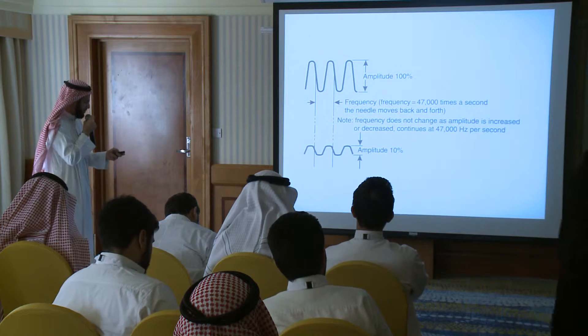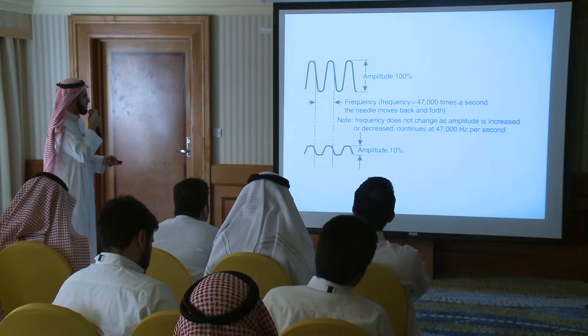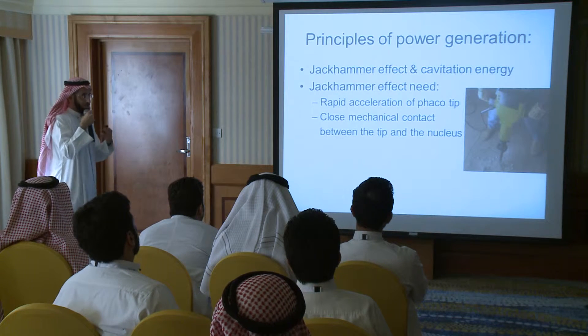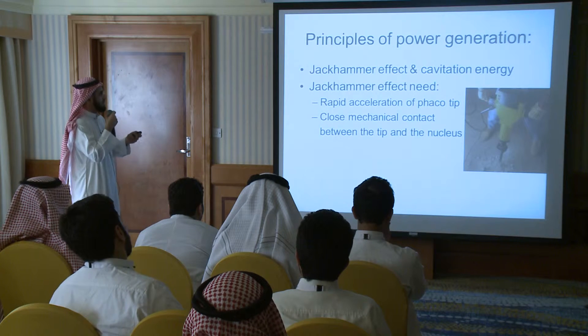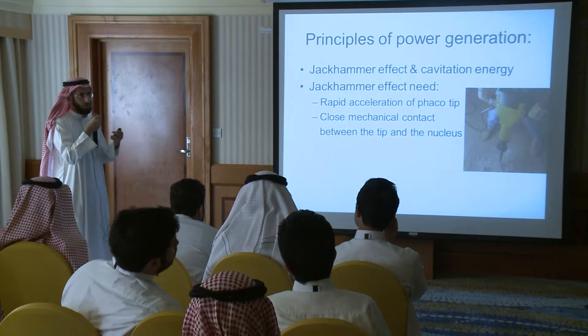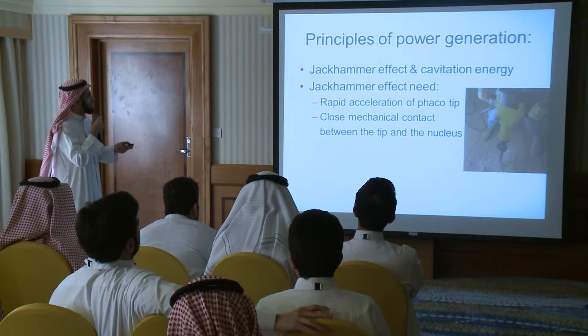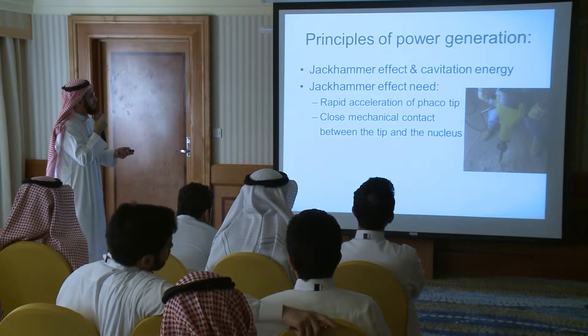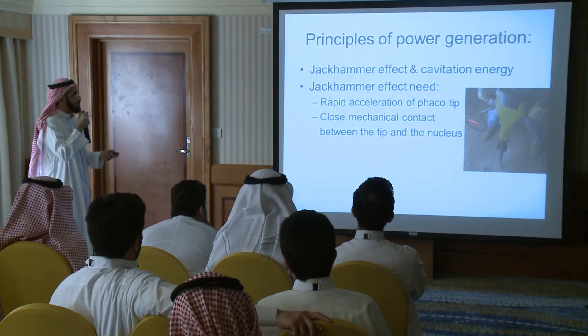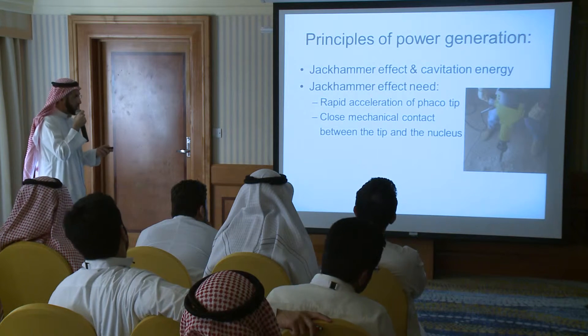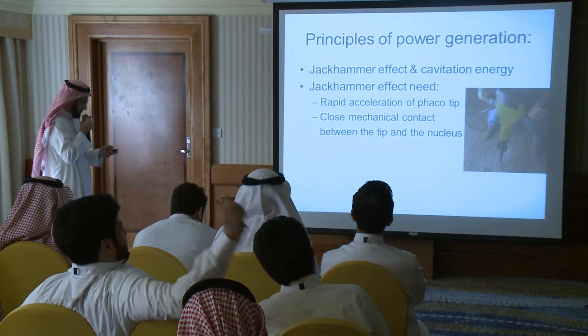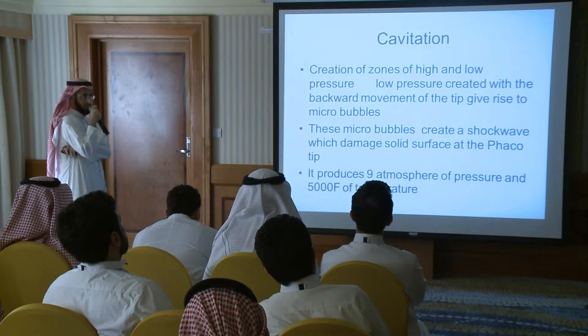How do we generate the power? Power is very important to emulsify the nucleus. We have what we call the jackhammer effect. The jackhammer effect requires rapid acceleration of the phaco tip and close mechanical contact between the tip of the phaco and the nucleus.